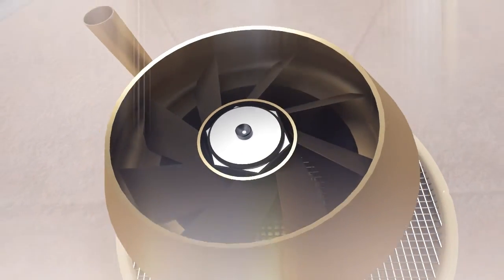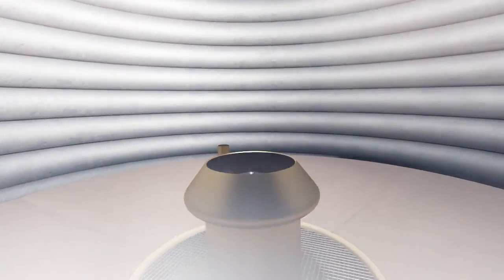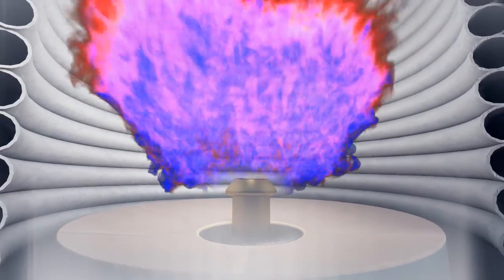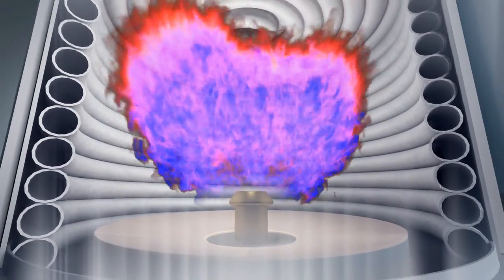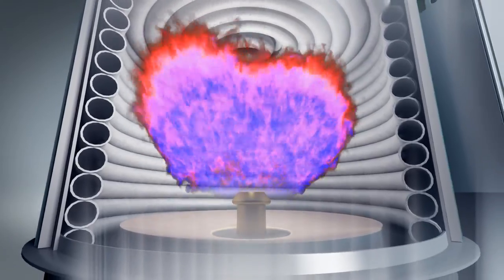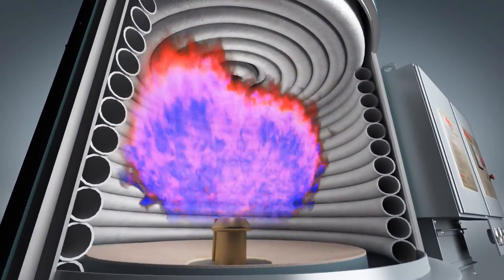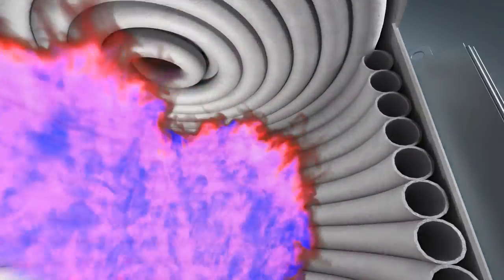The water flows straight through in a counter-flow path to the combustion gases. The bottom section of the coil assembly is a water wall section that forms the combustion chamber. Heat from combustion is transferred into the water flowing through the coil in a counter-flow path.